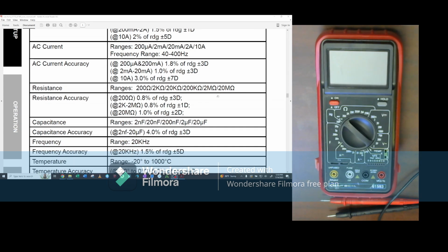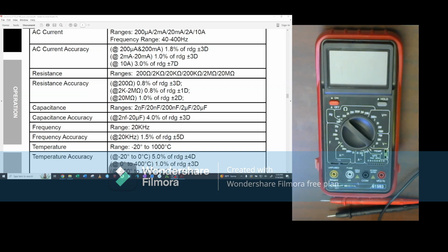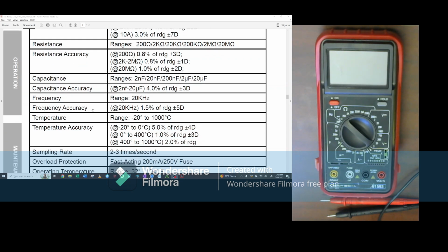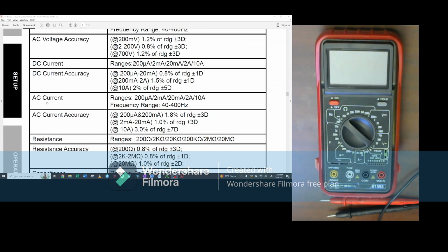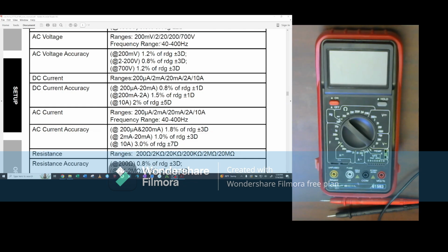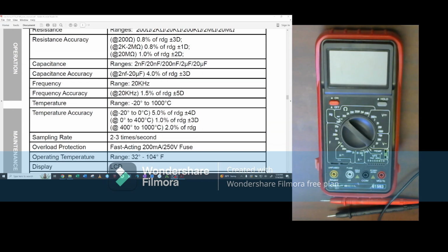We have resistance measurements that we can measure up to. In this case, it gives us the different ranges, with the maximum being our 20 megohms. We've got our capacitance measurements. We can measure into the 2 nanofarad range all the way up to the 20 microfarad range. However, if we are just curious what the frequency is and we're wanting to use the DMM to determine that, this has a maximum frequency range of 20 kilohertz. So if we're just measuring frequency, it can go to 20K. If we want to come back up here and measure AC current or voltage, then we have to take into account that 400 hertz limit that we have for those functions. So frequency by itself will just give us an accurate measurement up to 20K. If we want AC measurements, it has to be below 400 hertz.